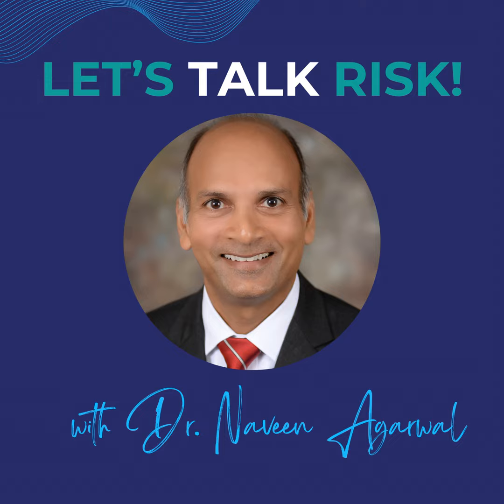Got it. So you've got this device using complex eye data, software interpretation, giving a result to help diagnose something serious, where a wrong answer, especially that false negative, carries significant risk. Feels like the quality system needs to be absolutely watertight. You'd think so. Which brings us to that warning letter, issued May 9th, after an inspection earlier in 2025. And the verdict was? Adulteration, basically, failure to comply with quality system regulation, 21 CFR 820, and misbranding as well.